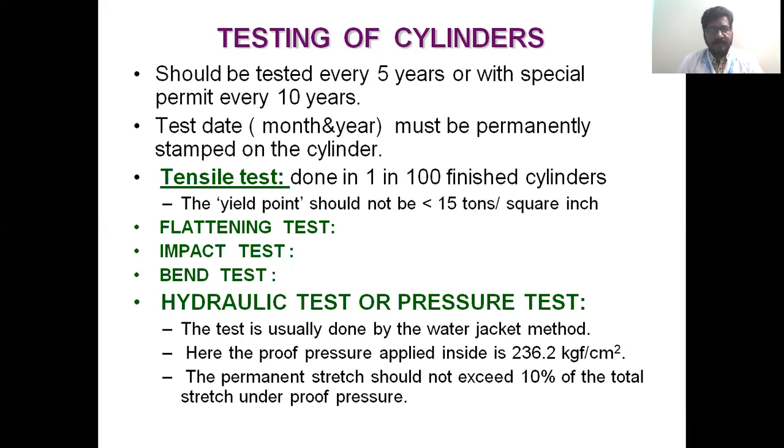The following are the different types of tests being used to test the tensility, to test the durability of the cylinder. Namely, tensile test, which is done in 1 in 100 finished cylinders, and flattening test, impact test, bend test, hydraulic pressure test.